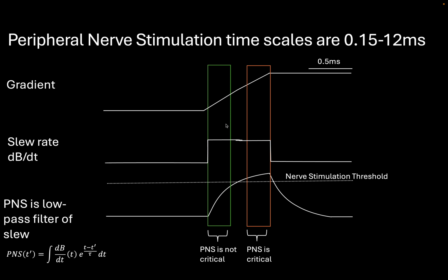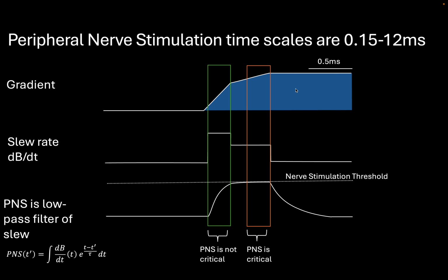So going from this slow increase that exceeds the PNS to something like fast increase and then slow allows you to increase to the same gradient strength in the same time, while not exceeding your PNS, still giving you this huge gradient moment, which is the equivalent of having high resolution. So this tuning step allows you to basically break the barriers in spatial resolution.